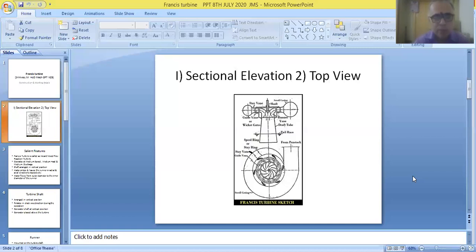So therefore, if the area of cross section increases, the kinetic energy of the liquid decreases, and the pressure energy of the liquid increases. So this is useful for recovering the pressure of the liquid. It's useful for destroying the negative pressure of the liquid. So therefore, these divergent draft tubes are used for operating the Francis turbine.